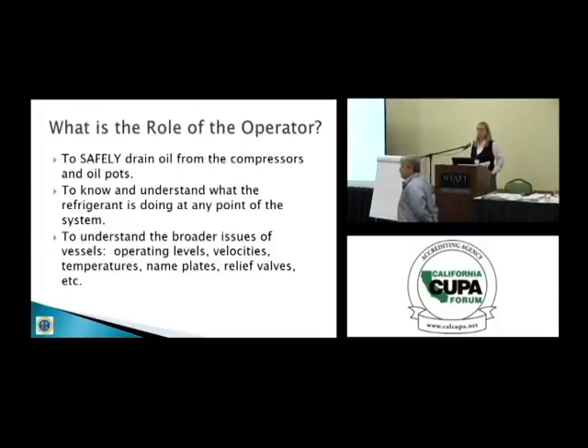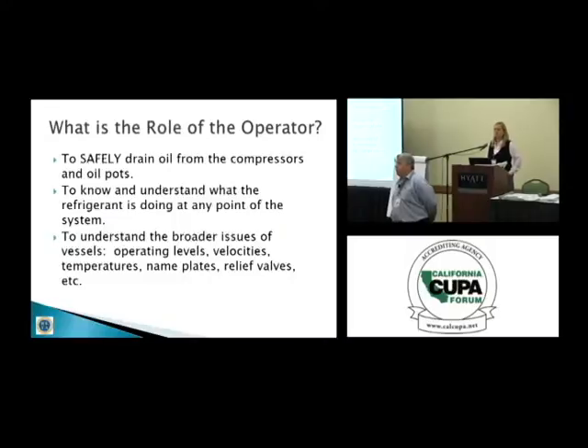With the equipment that I'm responsible for, I'm replacing a lot of nameplates. And the cost of replacing a nameplate, my most expensive one, has been about half the price of the vessel, just because of where it was and the cost of getting that certified individual out there. It was about $2,000, I believe. But the point is there is a process, and you start with the National Board and download their form for requesting a duplicate or a replacement nameplate.